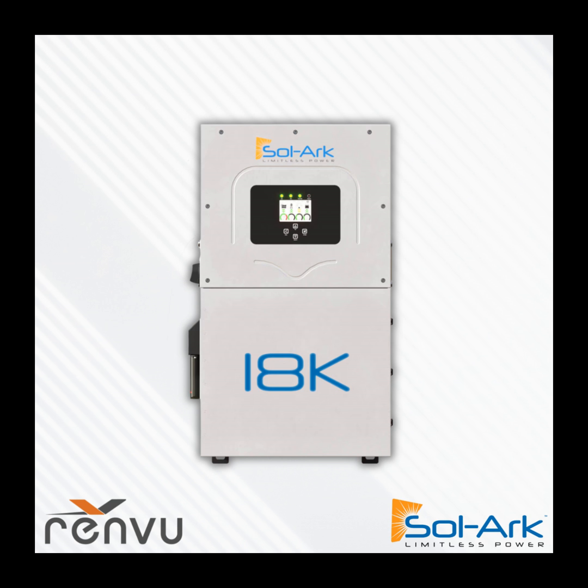So we have 6 solar ports on the Sol-Ark inverter, and what I recommend is just sticking to 6 strings. Not that you couldn't parallel more strings up on the rooftop, but then you have to get into fusing and combiner boxes, and it complicates the project. I would just keep it simple, 6 strings, bring them down to the inverter and land directly onto the inverter.